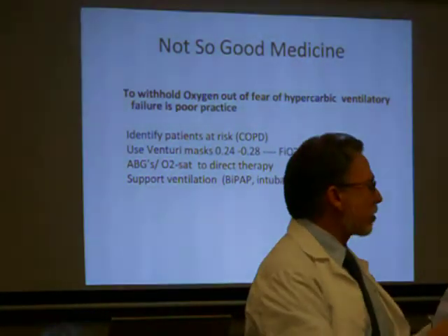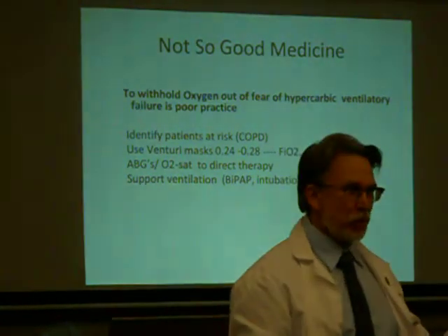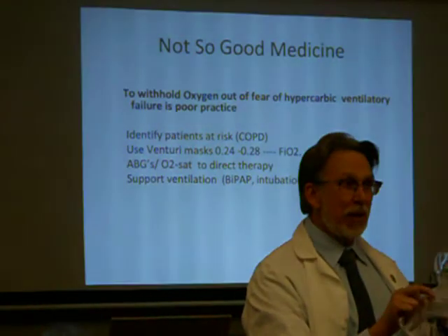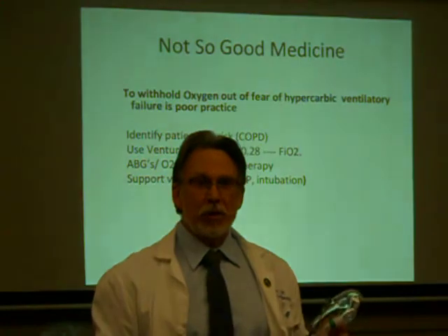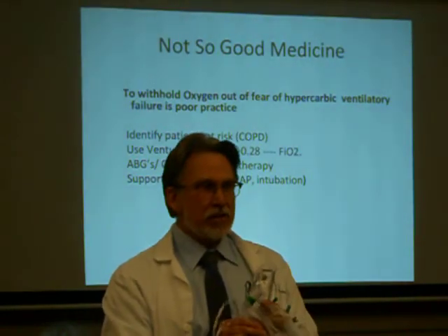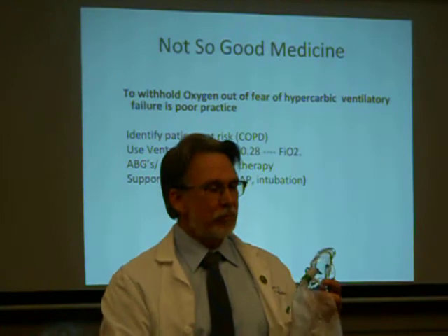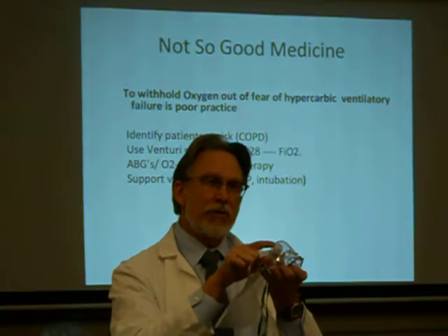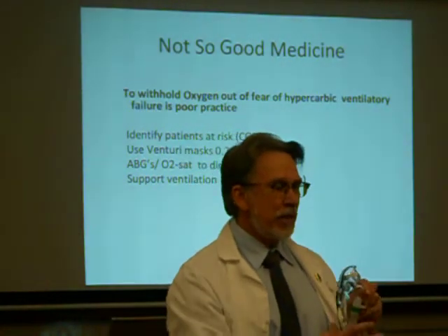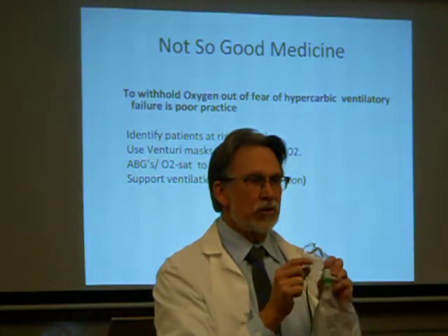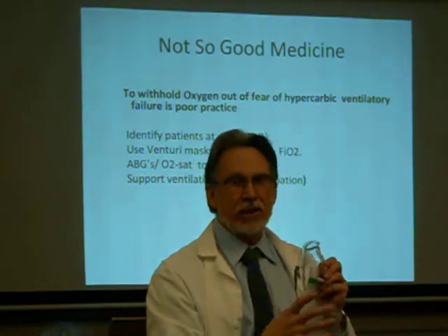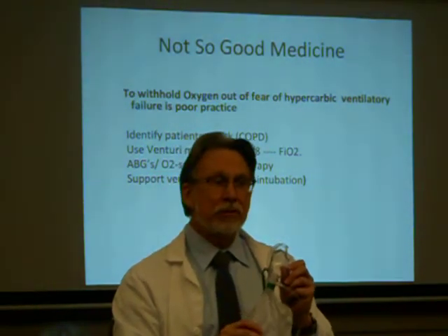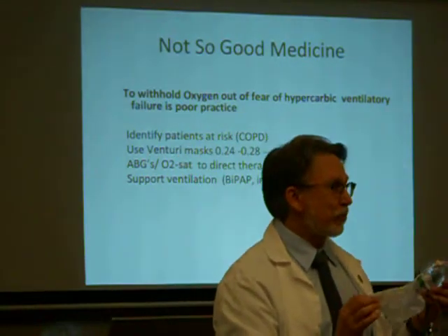Now, how does this one work here? Usually you'll see the respiratory therapist set it up. There's a flow that comes in, it fills up the bag, and the therapist will watch to make sure that the bag doesn't empty completely with each breath. I'll pass this around also, but there's a one-way valve here which allows someone to inhale from the bag, but the exhalation goes through these little holes here. So they're just inhaling from the bag. When this is full, there's like a reservoir here, so you can breathe 100% oxygen.